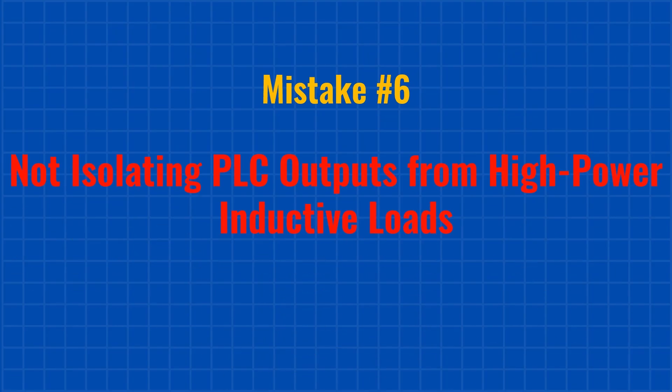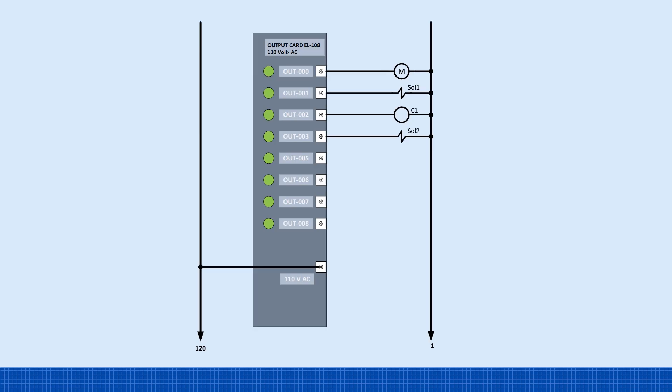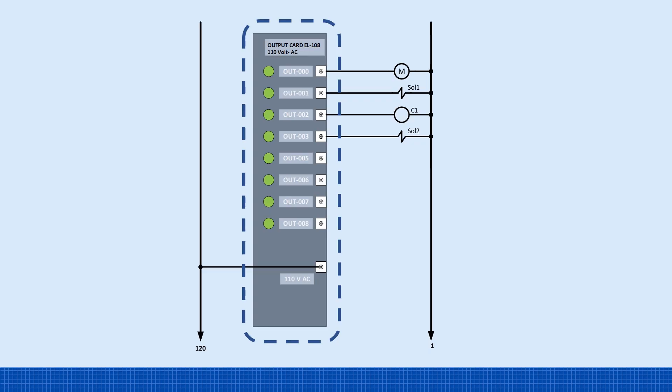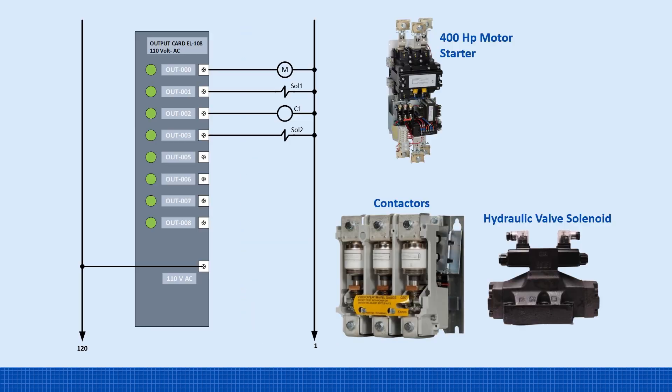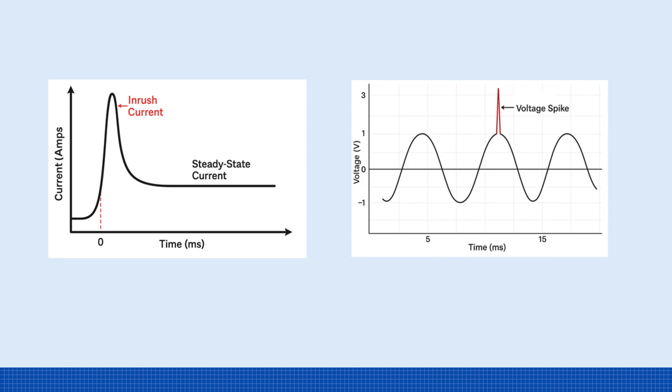Mistake number six. Not isolating PLC outputs from high-power inductive loads. This is usually a design issue, and it often comes down to cutting costs. PLC output cards use electronic components like transistors to switch loads. Some may have relay outputs, but those relays are small and not built to handle high currents. Inductive loads, like motor starters, contactors, and large solenoids, create high inrush currents and voltage spikes during switching. For example, a contactor coil rated at just 0.5 amps can pull up to 5 amps during inrush. These spikes can slowly damage the PLC output card, leading to failure over time.